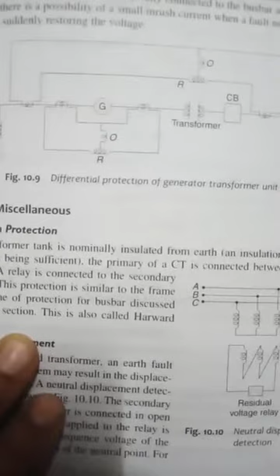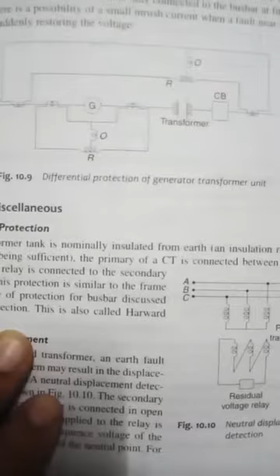You can see here a diagram. This shows an overall differential protection scheme. Usually harmonic restraint is not provided because the transformer is only connected to the bus bar at full voltage. However, there is a possibility of small inrush current when a fault near the bus bar is cleared, suddenly restoring the voltage.